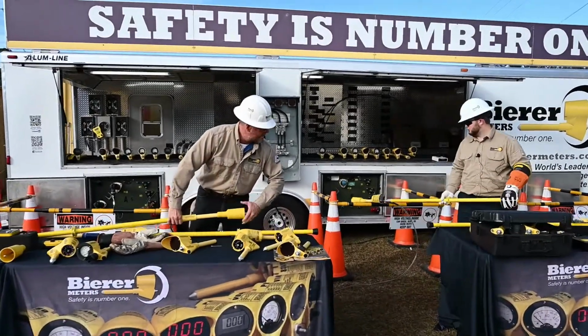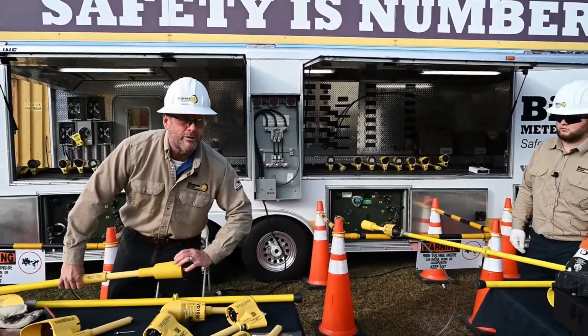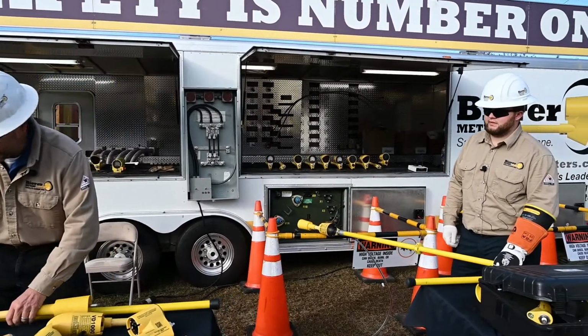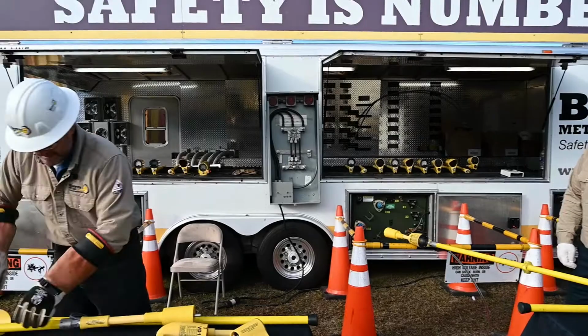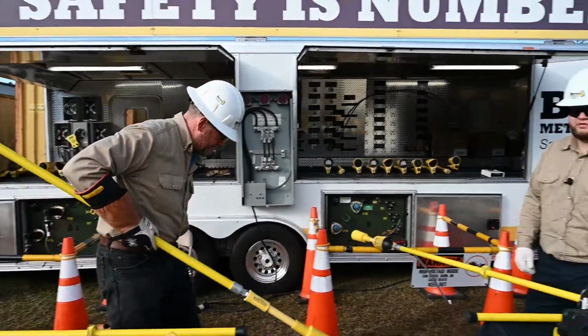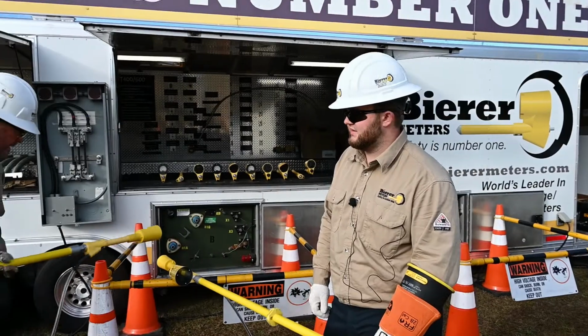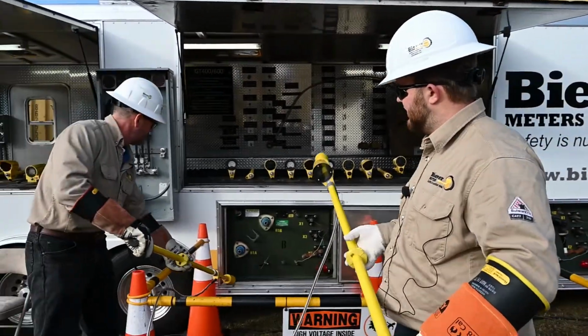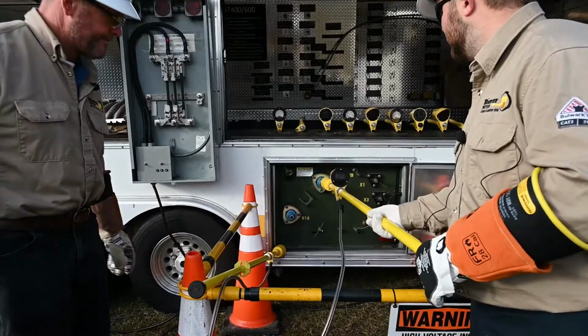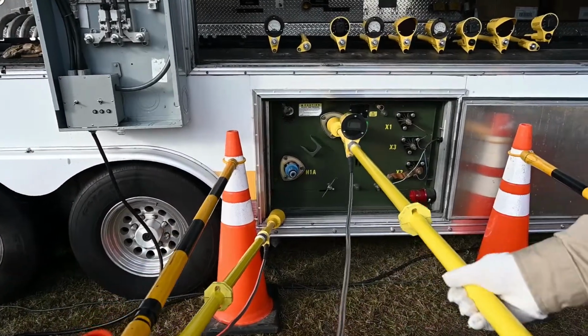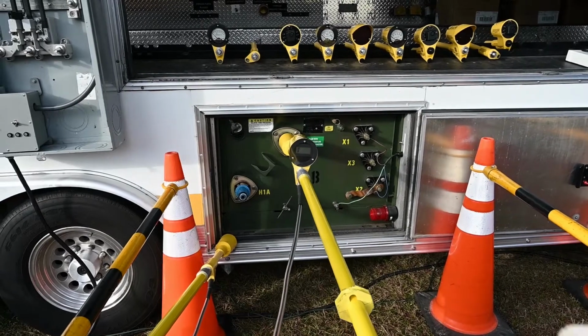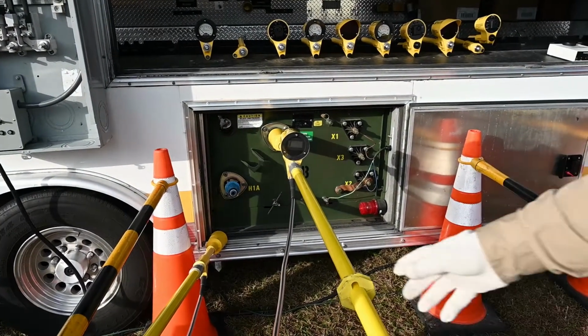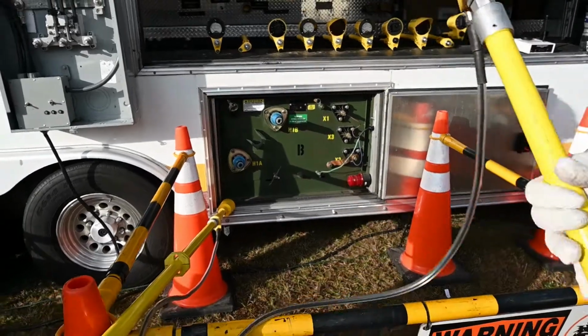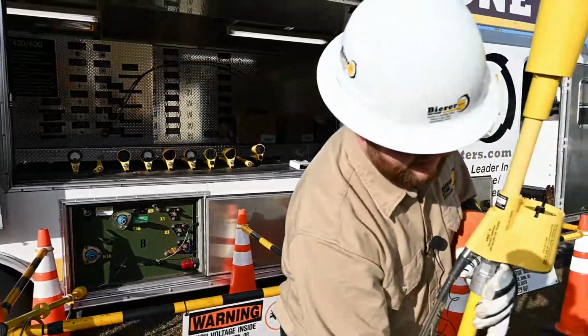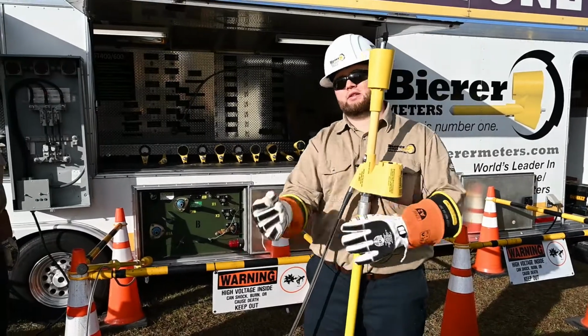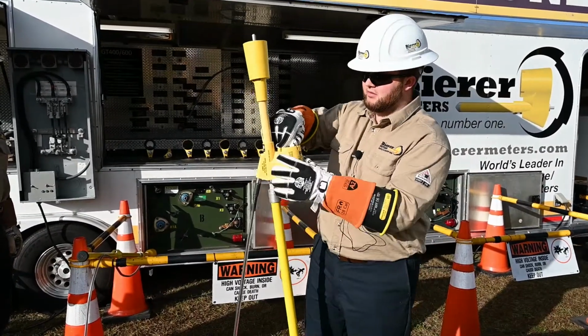So what we're going to do is go over the primary power, overhead, underground, it doesn't matter. Show you guys. Again here, primary voltage, we're going to go phase to ground first for the same reasons. We're going to verify the tool's working, and verify our head's in the game. So make contact. We get a 1 at first. I've still got this tool in the secondary setting, the 2 kV setting. We get a 1. It's telling us the tool's in the wrong setting. It's not actually broken, it's just giving us a funky reading to let us know it's in the wrong setting.